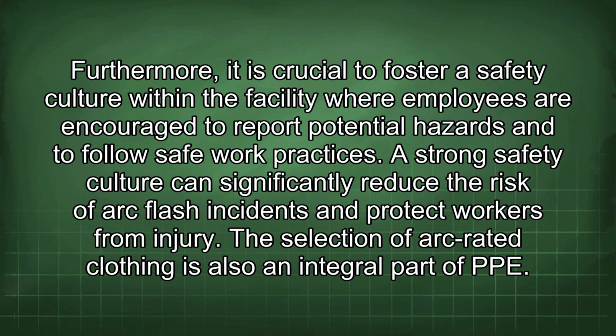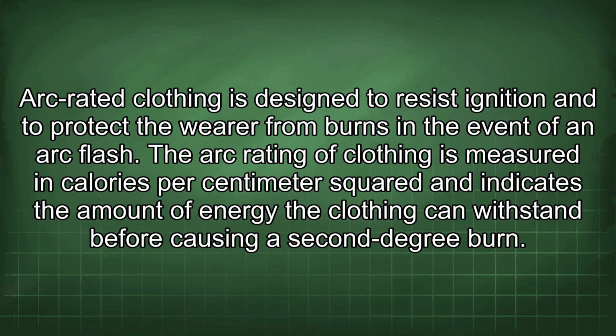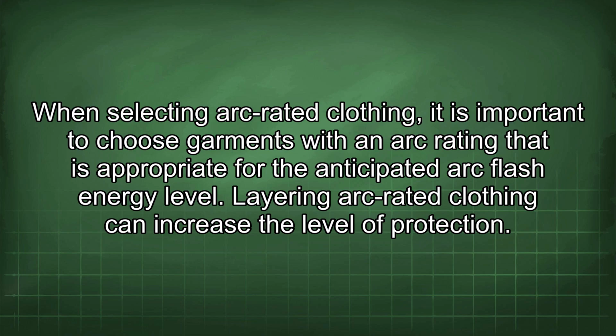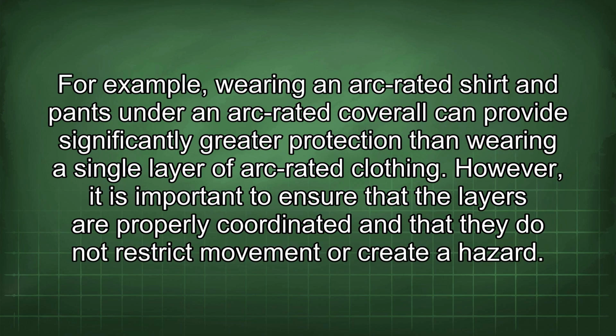The selection of arc-rated clothing is also an integral part of PPE. Arc-rated clothing is designed to resist ignition and to protect the wearer from burns in the event of an arc flash. The arc rating of clothing is measured in calories per centimeter squared and indicates the amount of energy the clothing can withstand before causing a second-degree burn. When selecting arc-rated clothing, it is important to choose garments with an arc rating that is appropriate for the anticipated arc flash energy level. Layering arc-rated clothing can increase the level of protection. For example, wearing an arc-rated shirt and pants under an arc-rated coverall can provide significantly greater protection than wearing a single layer of arc-rated clothing.